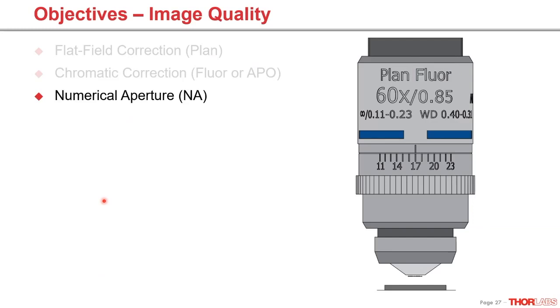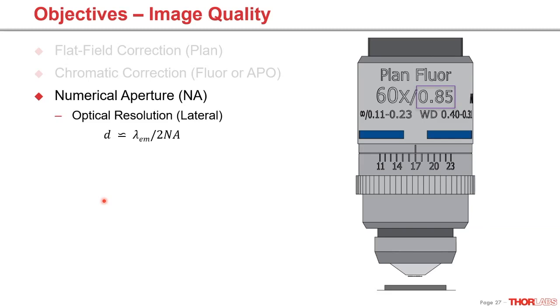Numerical aperture (NA) is an important parameter extensively discussed in our first webinar. NA plays a role in optical resolution — in fluorescence microscopy, lateral resolution is emission wavelength divided by two times the numerical aperture. A higher numerical aperture gives you higher or finer optical resolution. At the end of the day, this optical resolution is a physical limit ruled by the diffraction of light, so it's the emission wavelength that determines the physical limit — you won't be able to get anything smaller than half of that.